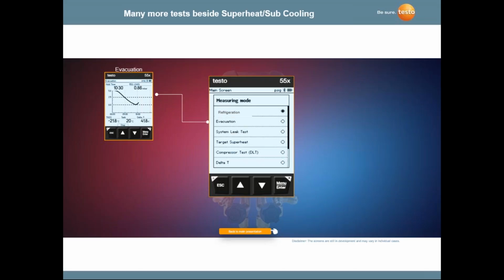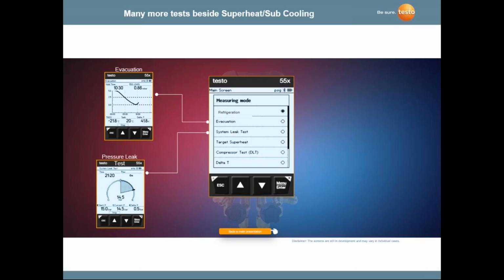We can do a long test. We can graph the test after it reaches a certain point. We can look at a decay rate alarm. So if the vacuum starts to increase and passes that decay rate, it's going to alarm your cell phone. Keeps continuous operation, continuous measurement of the vacuum. A pressure test. A lot of you may be using nitrogen to pressurize the system. You can pressurize the system at 300 PSI. There's a built-in clock in the instrument, so you turn on the clock, and over a period of time, you're going to see if there's any pressure loss over a period of time when you're doing a nitrogen pressure test.